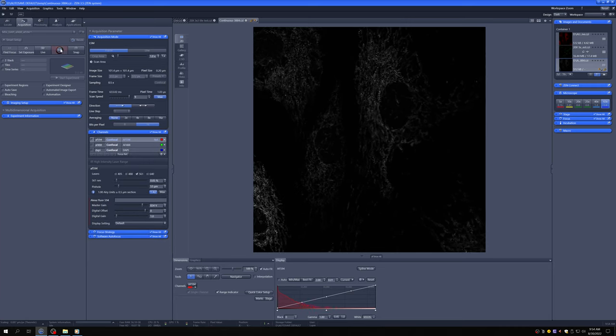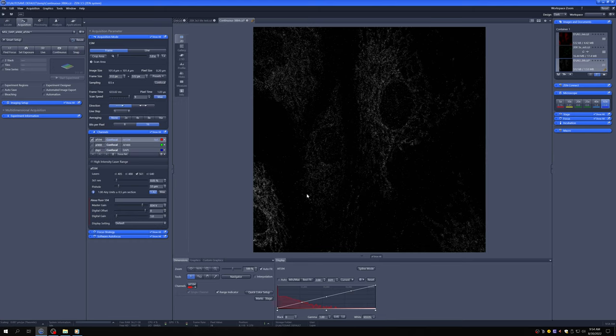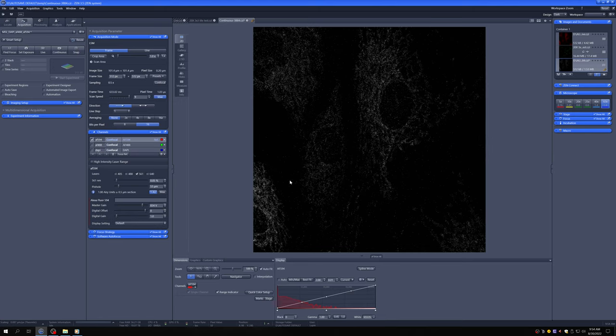The point I want to make is that the more you average, the better the image looks, but by a smaller and smaller amount. The difference between no averaging and 2x is usually bigger than the difference between 2 and 4x, which is bigger than the difference between 4 and 8x and 8x and 16x. So there's sort of diminishing returns to averaging. The other point is that averaging has a very noticeable effect on images that are very noisy to begin with, but it doesn't have such a noticeable effect on images that are already quite good. So diminishing returns and stronger effects on things that are noisy. Those are two characteristics of averaging.